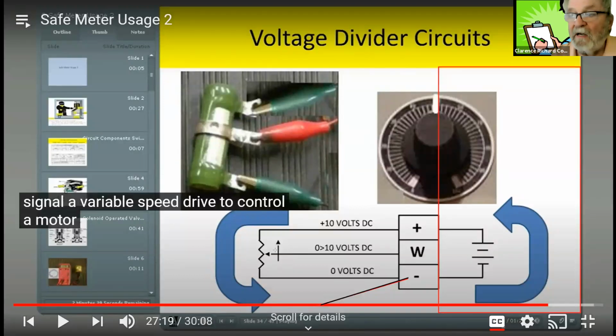So you can either put it at the W for the wiper, or you can put it right there at the pot wiper. Say we put it at the pot wiper, and I tell you that you have 0 volts DC. Then what are you going to do? Have you determined anything, or do you have to keep on checking? Keep checking. Okay, so was that a good reading or a bad reading? It was a bad reading. You were expecting 5, you got 0. That's a bad reading. Where are you going to check next?